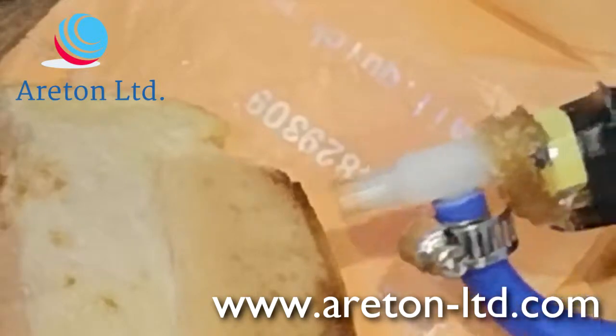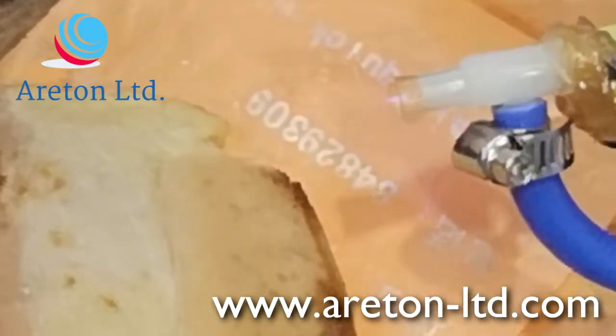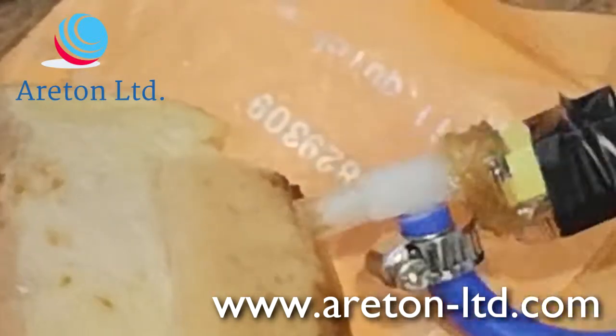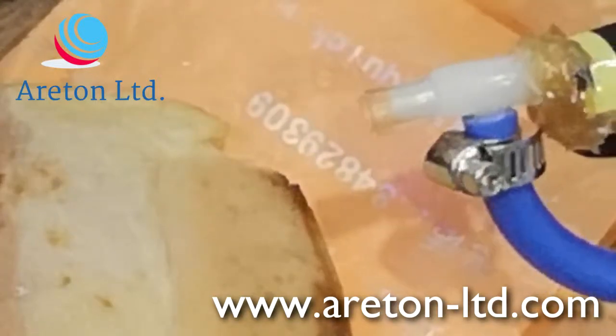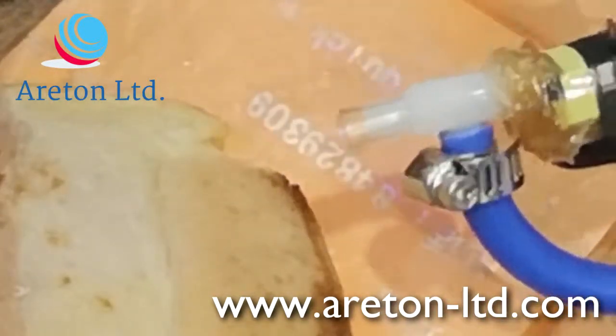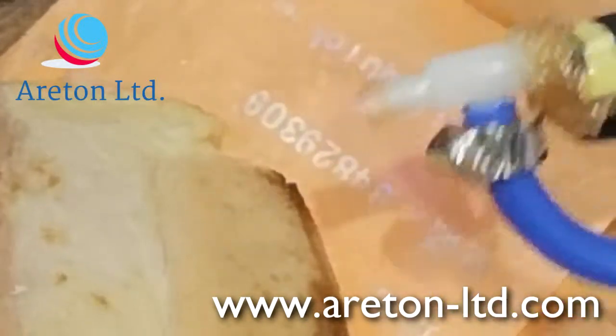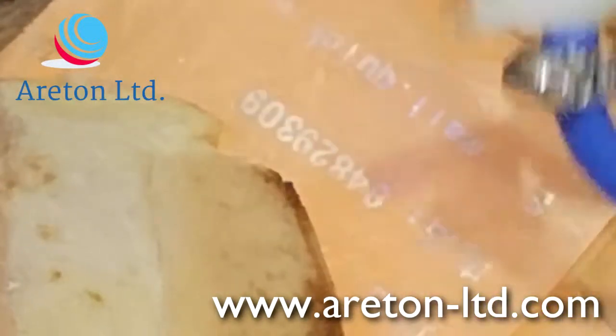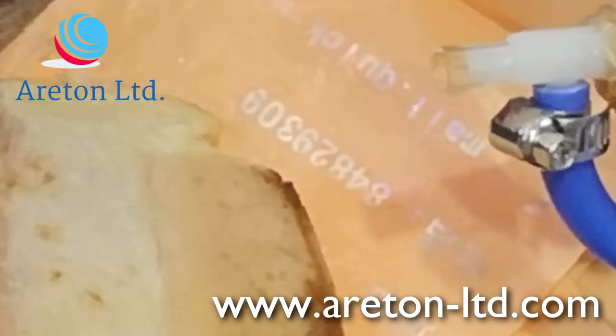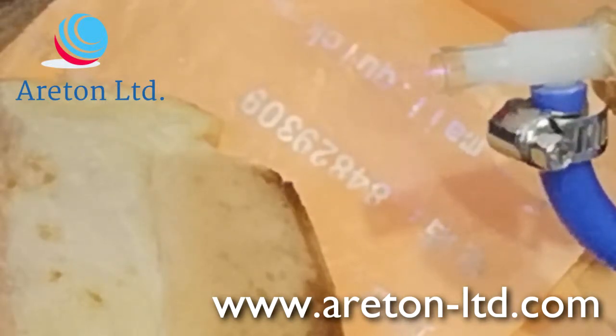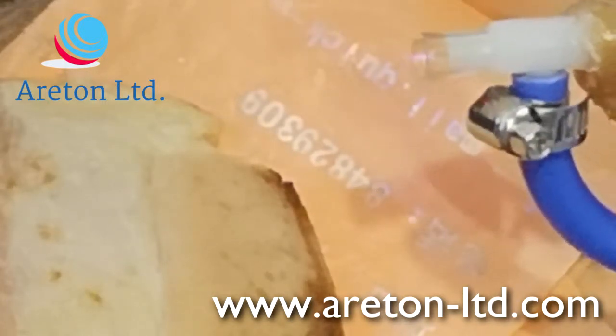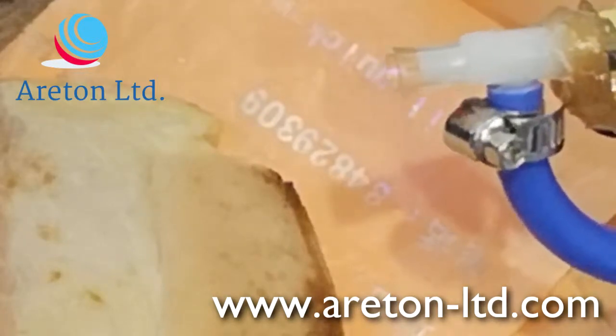It detects the arc. It's off. Now it's on. And it's off. Do it again. Okay, it hasn't detected it because you haven't heard the beeping. It's detecting it now. So maybe the first 2 arcs were in the region of 400 milliseconds, the last one about 100 milliseconds approximately. Just do it again.